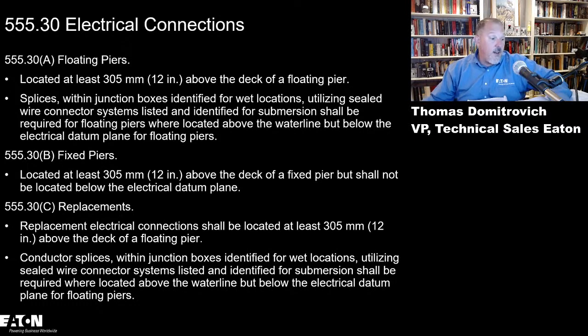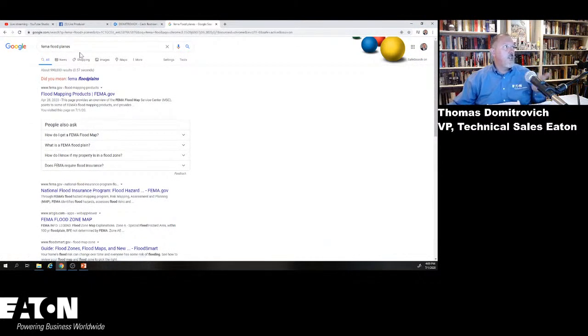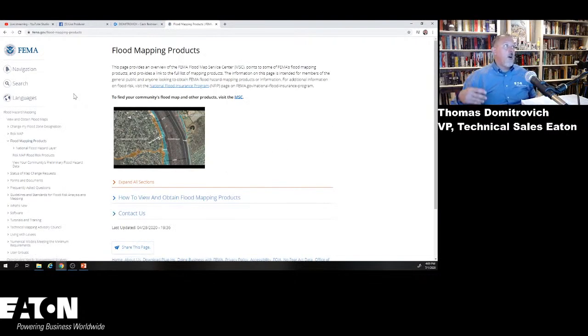I'd offer that for your electrical datum plane, you can just Google FEMA floodplain, there's flood mapping. Some jurisdictions use this, and again this will vary because it's not defined in the National Electrical Code. The NEC doesn't tell you how to establish that floodplain value, and it's debated on what to use. FEMA's numbers and levels are argued by some to be unrealistic, way too high, resulting in receptacles on pedestals sticking way up in the air that aren't usable, or being unable to put certain service equipment anywhere near the water because of where FEMA has established those floodplains.